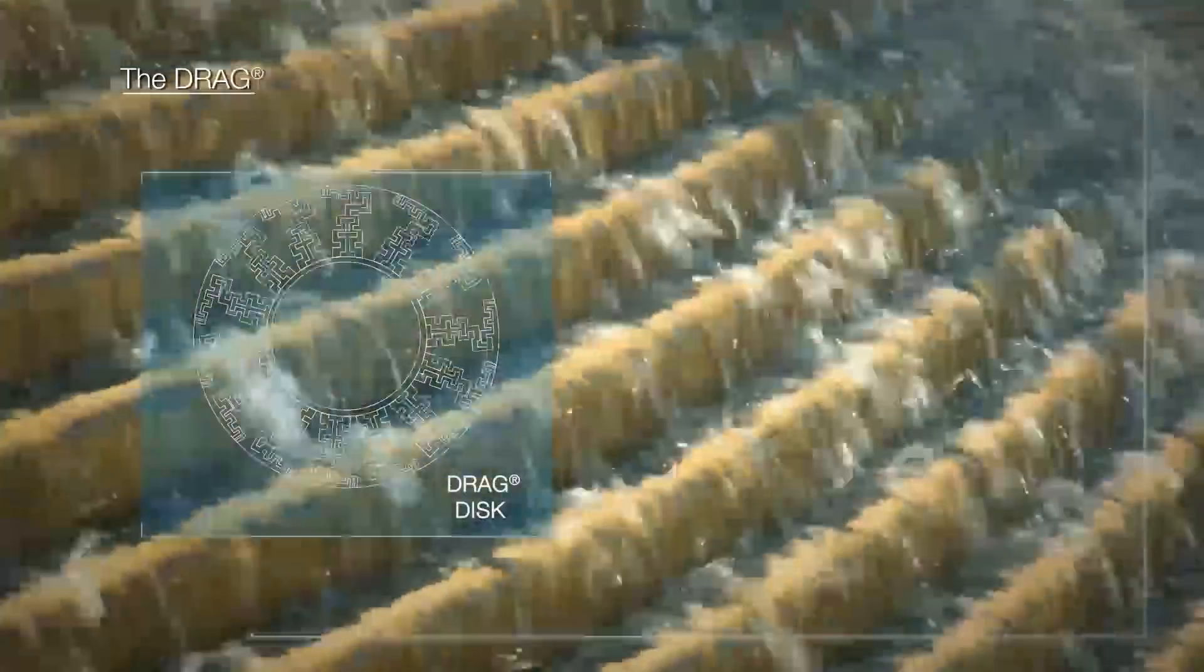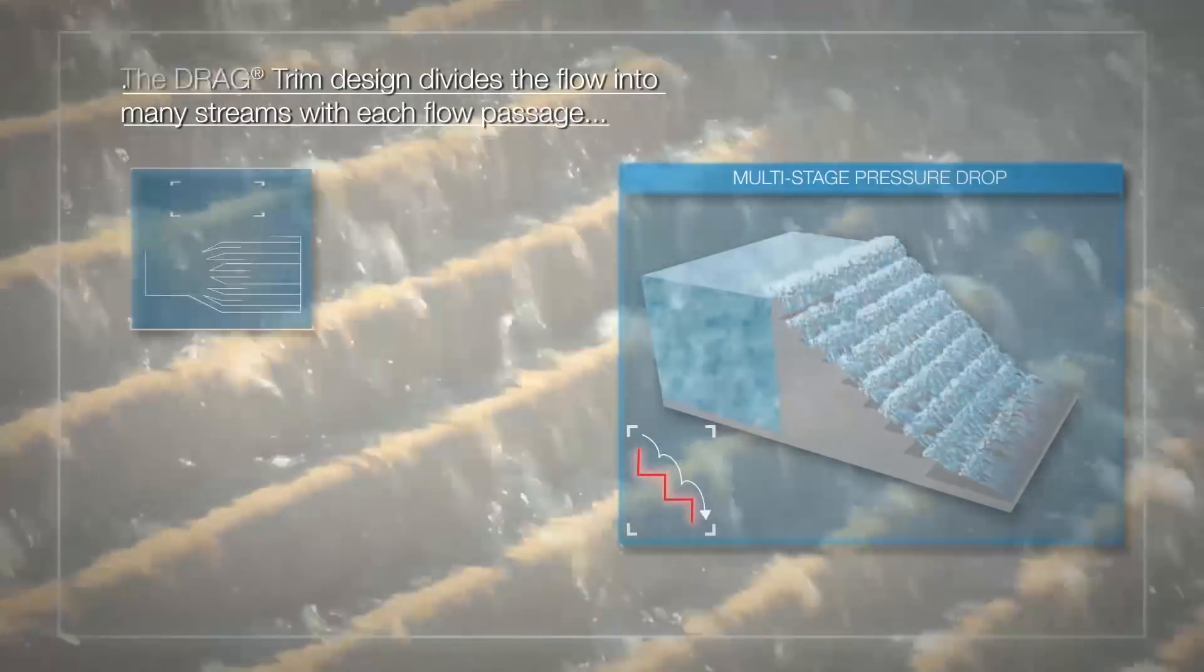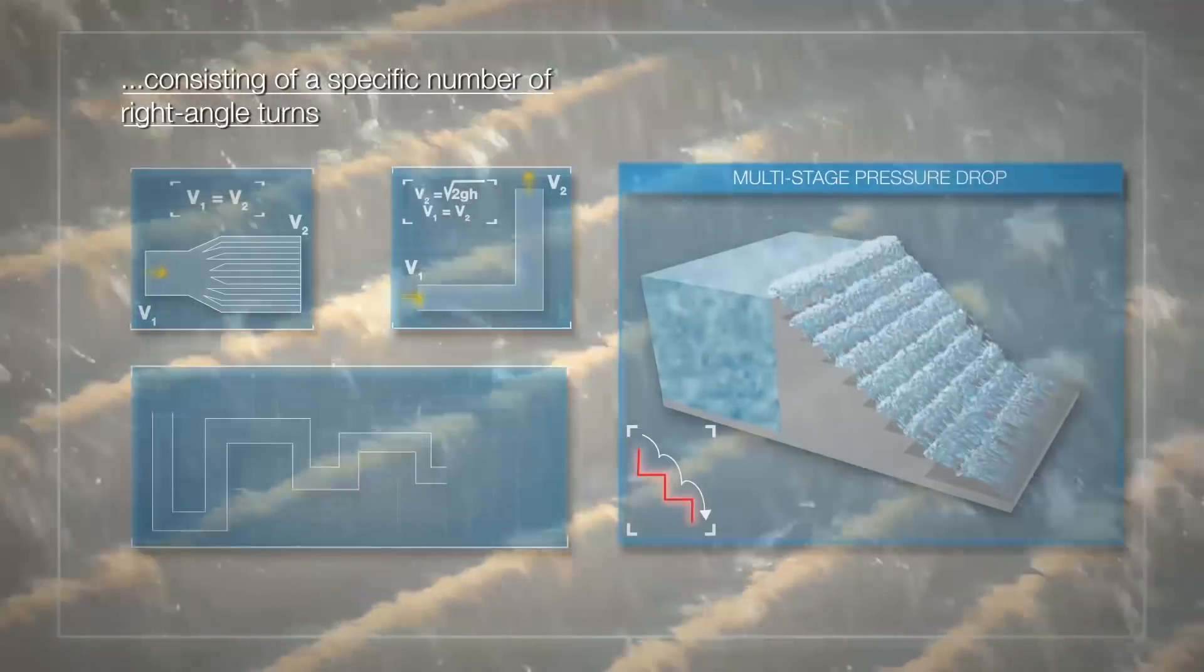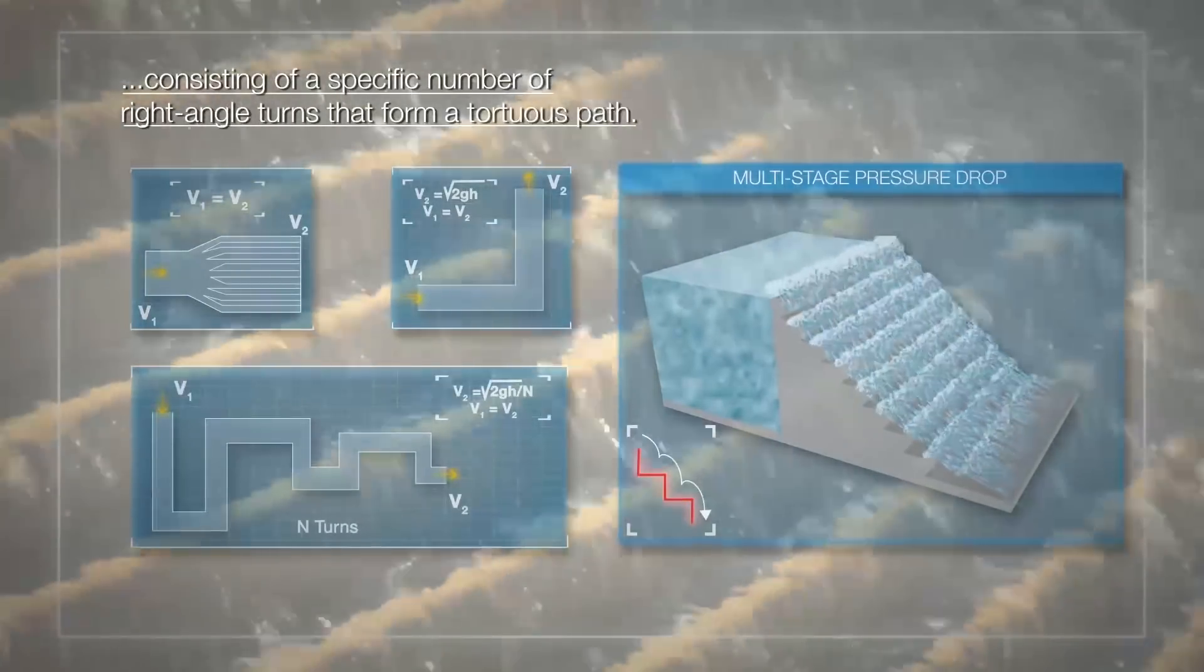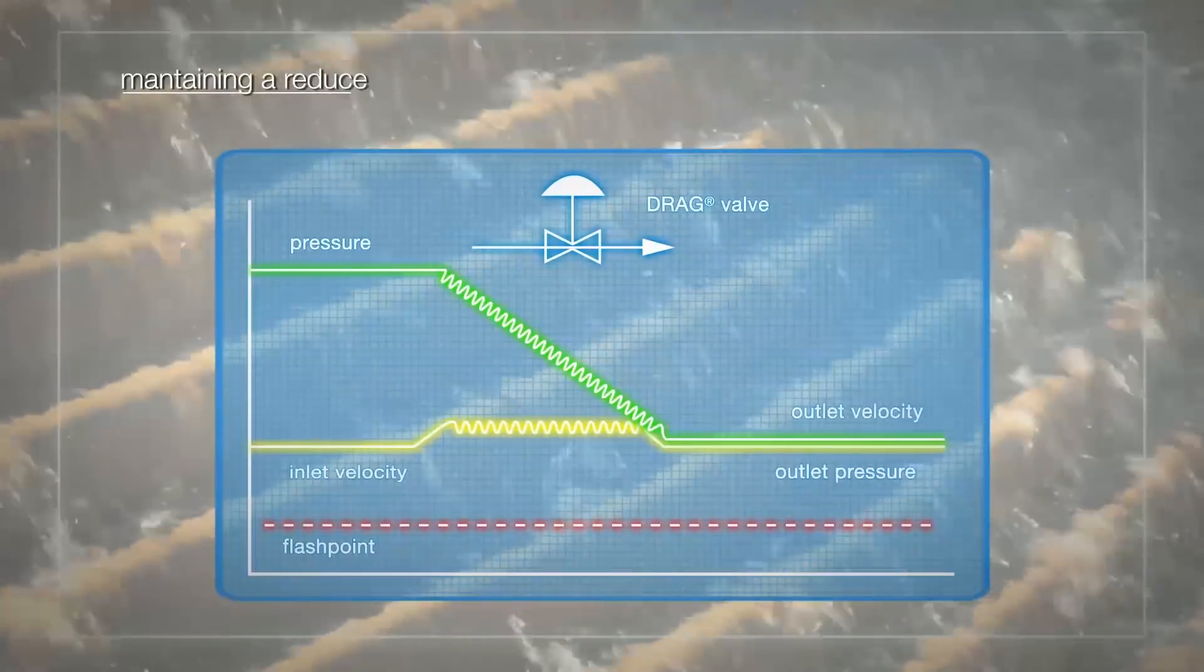The drag trim design divides the flow into many streams, with each flow passage consisting of a specific number of right-angled turns that form a tortuous path. This tortuous path achieves the necessary pressure reduction while at the same time maintaining a reduced fluid velocity.